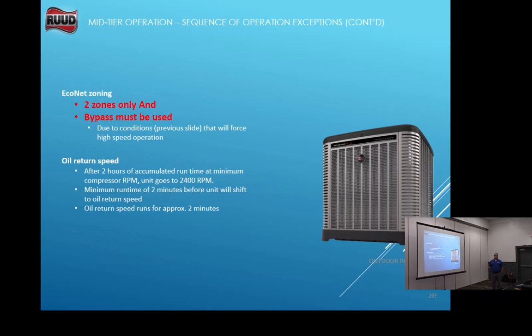If you do any zoning at all, the 15 and 16 SEER systems are 2 zones only, and it has to have a bypass. 2 zones only, and it has to have a bypass. You cannot put, yes, sir. Why is that on the 15 and 16? Because what are we trying to, what on that high-efficiency compressor, what was the biggest thing that jumped out at you and said that we don't want on that compressor? We don't want compressor flood back, right?